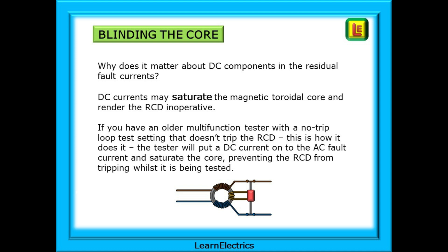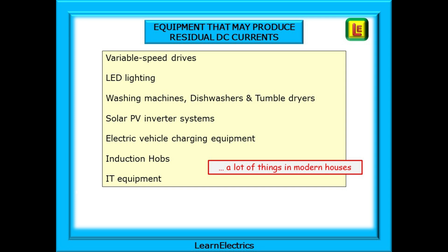If you have an older multifunction tester with a no-trip loop test setting for measuring earth fault loop impedance — one that doesn't trip the RCD — this is how it works: the tester puts a DC current onto the AC fault current and saturates the core, preventing the RCD from tripping whilst it is being tested. It will blind the core during the test. Types of equipment that might produce DC residual currents and potentially blind the core include variable speed drives, LED lighting, washing machines, dishwashers, and tumble dryers.